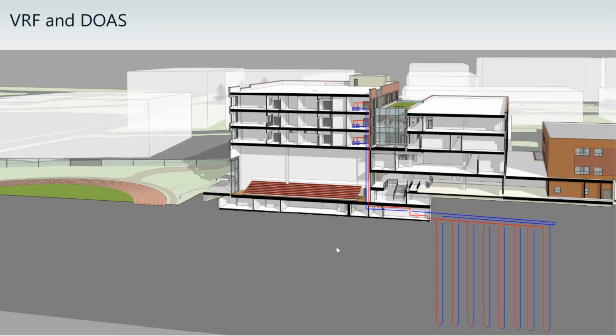So going back to this, we combined the variable refrigerant flow system with dedicated outdoor air systems with energy recovery. Those units, the energy recovery units and the ventilation air units, are in those floor-by-floor mechanical rooms as well. Having them floor by floor allows us to shut down floor by floor. It also allows operations and maintenance staff to gain access to these rooms, even in inclement weather.